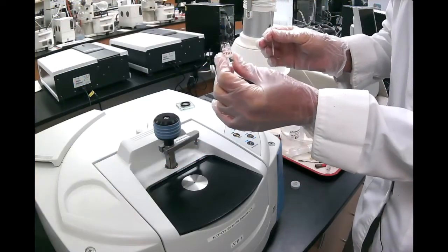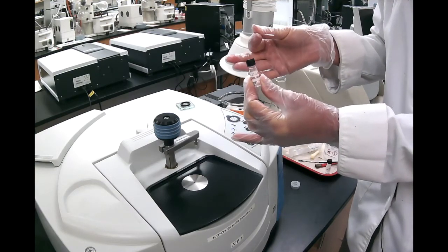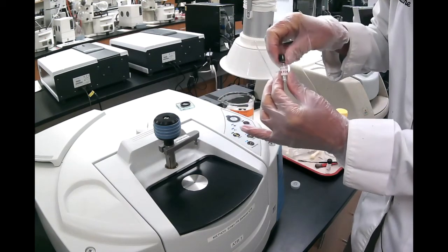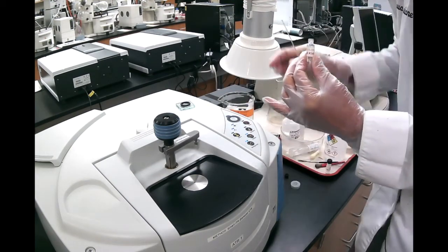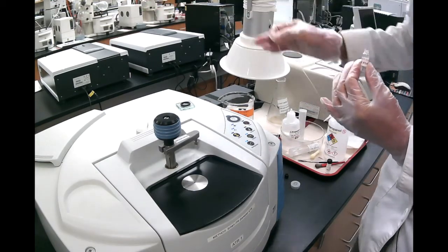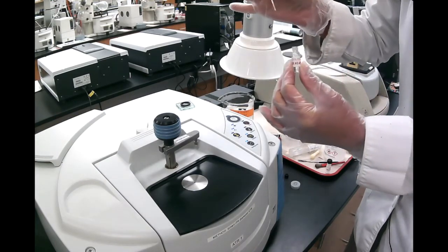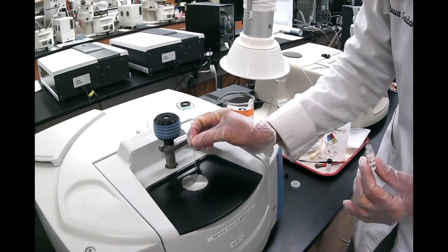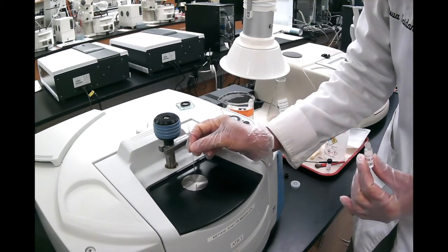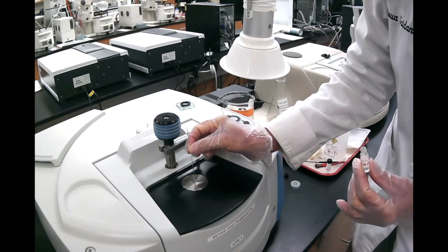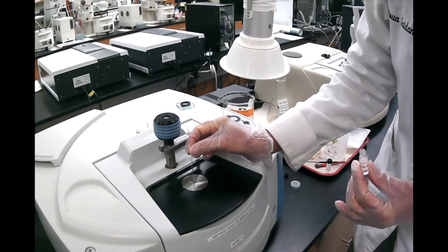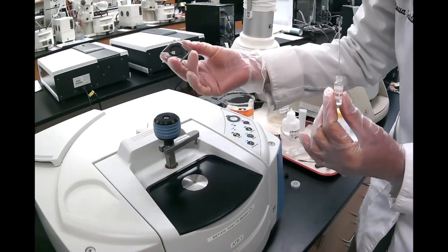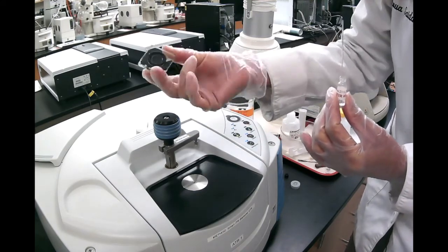So here I'm using a liquid sample. If you're doing the experiment where you have an unknown liquid, don't forget to write your number. Now, how do you put a liquid sample on your machine? You use an open capillary, and we have quite a few of them here. So you grab one, you put it in your sample, and then you don't want to touch the diamond directly. So the best approach is to touch the metal right on the perimeter. And you see there is now some liquid there. And try to be generous, because if you don't put enough, it might evaporate. But then if you wanted to avoid for it to evaporate, you have to cover it.